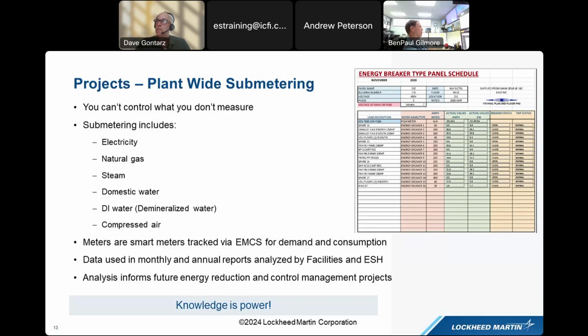We have over $10 million invested in submetering. You can see the different kinds of meters listed, in accordance with EPAct 2005 and EISA 2007 requirements for federal sites. This particular graphic interface shows one of our newer electrical panels. It shows every breaker, the breaker size, the amp draw, the kW, and whether it's open, closed, or normal. You can select any one of those points and it'll pull up a new graphic interface with 20 to 30 more points associated just to that one breaker. We can tell every aspect of what's going on in our electrical system using this kind of technology.